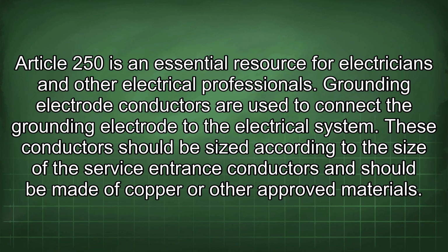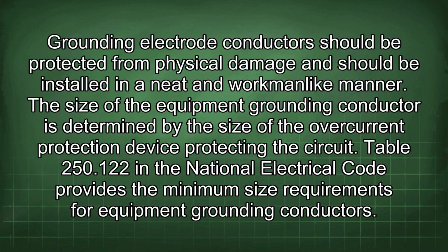Grounding electrode conductors are used to connect the grounding electrode to the electrical system. These conductors should be sized according to the size of the service entrance conductors and should be made of copper or other approved materials. Grounding electrode conductors should be protected from physical damage and should be installed in a neat and workmanlike manner.